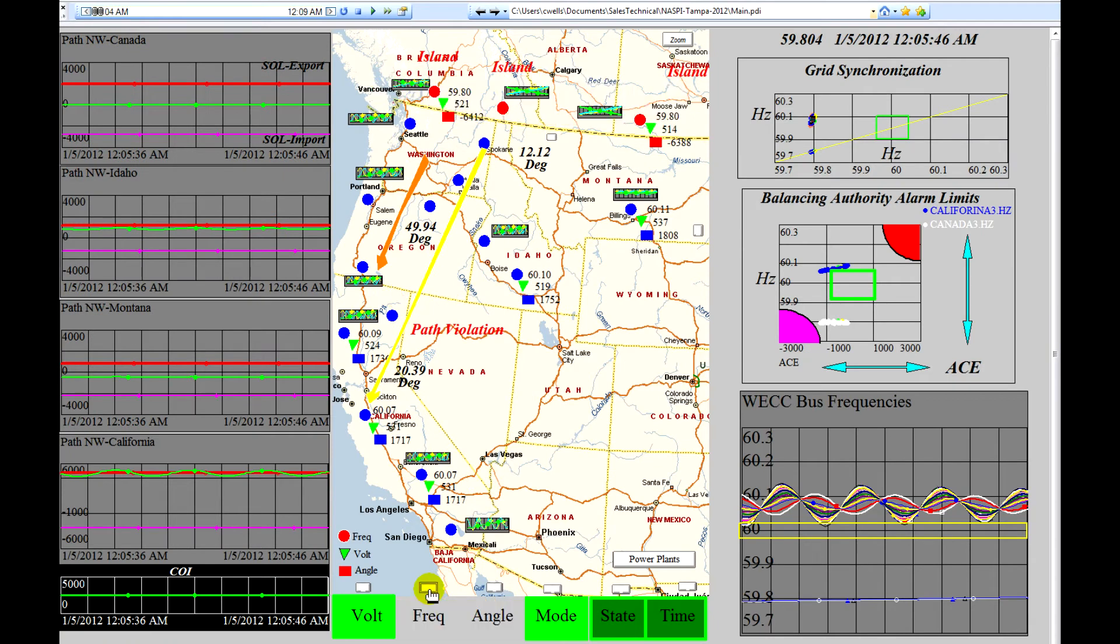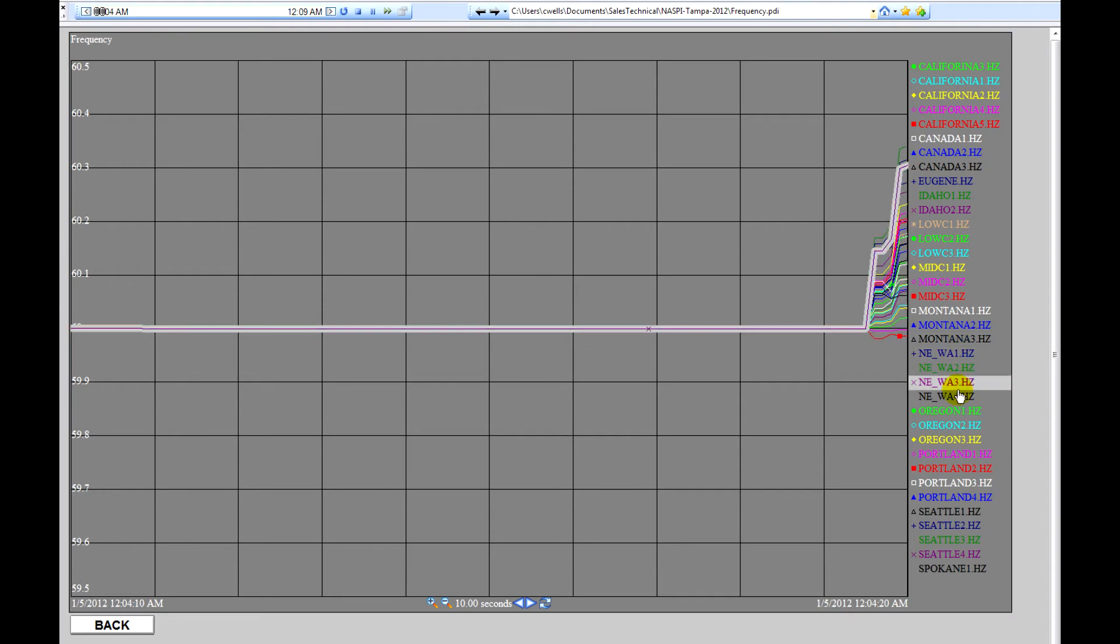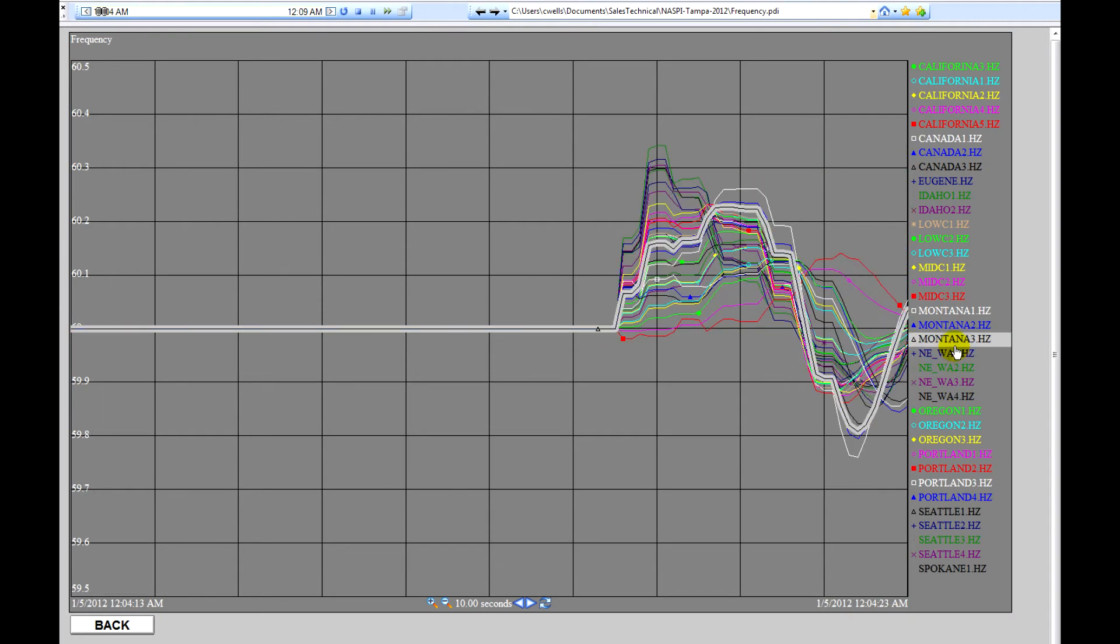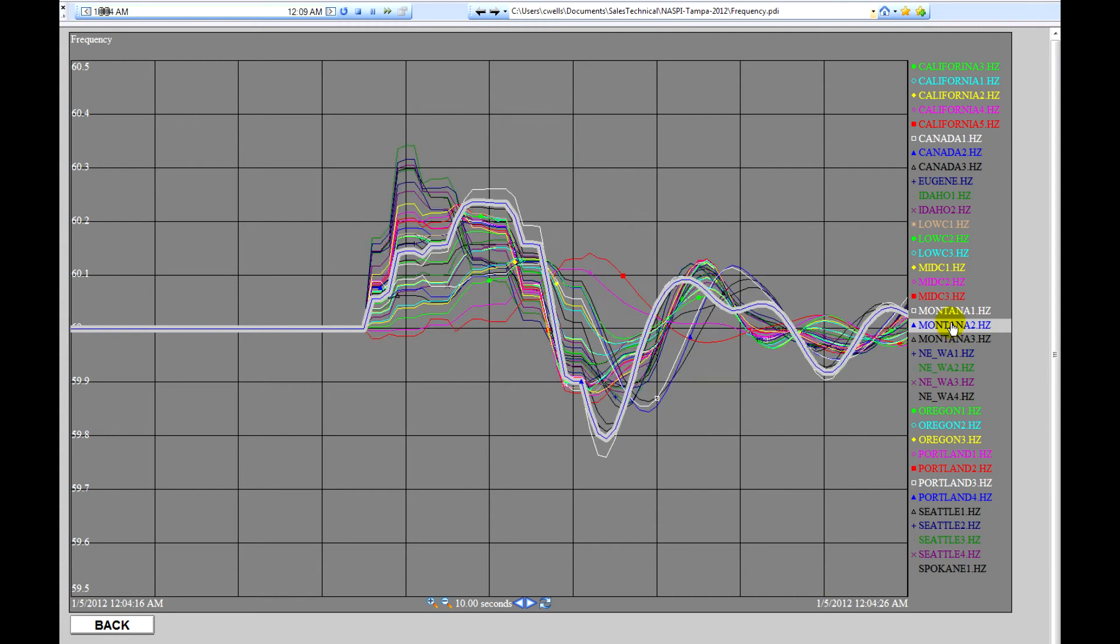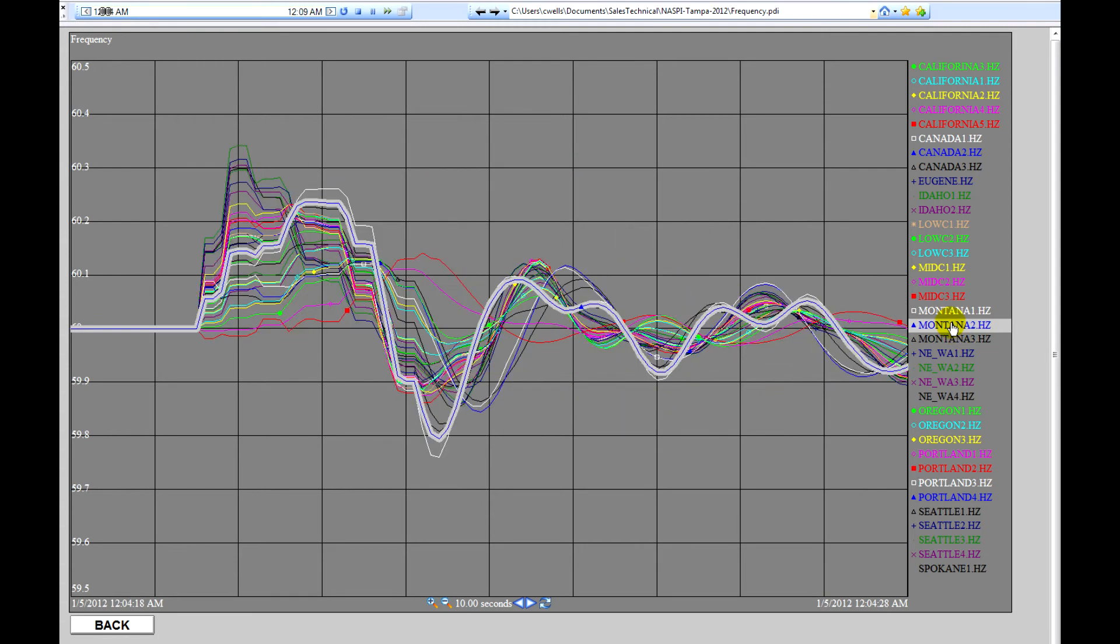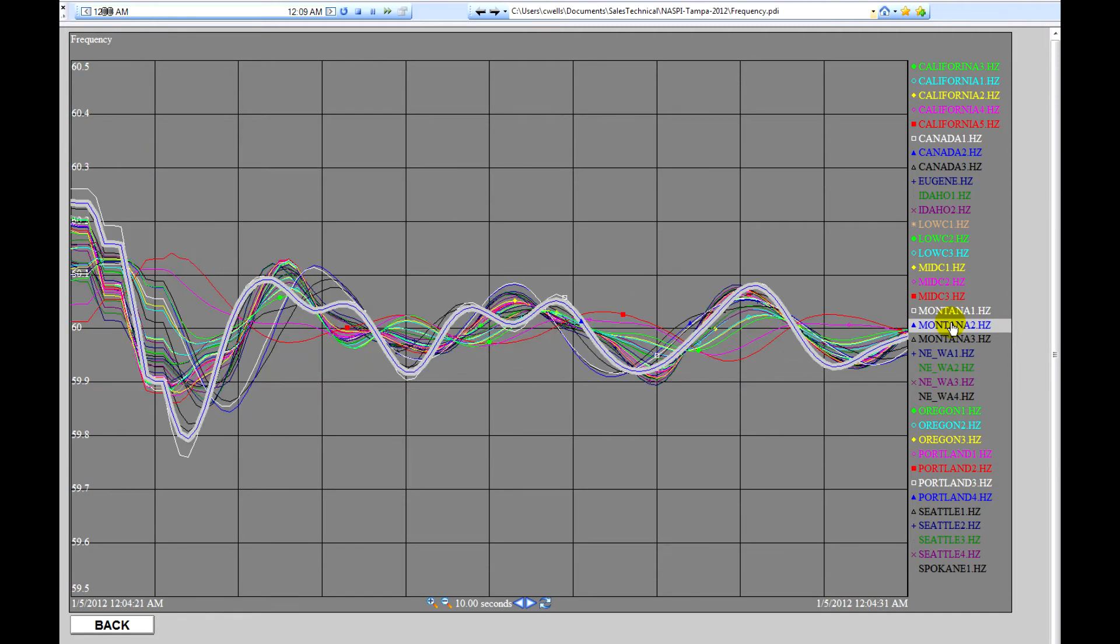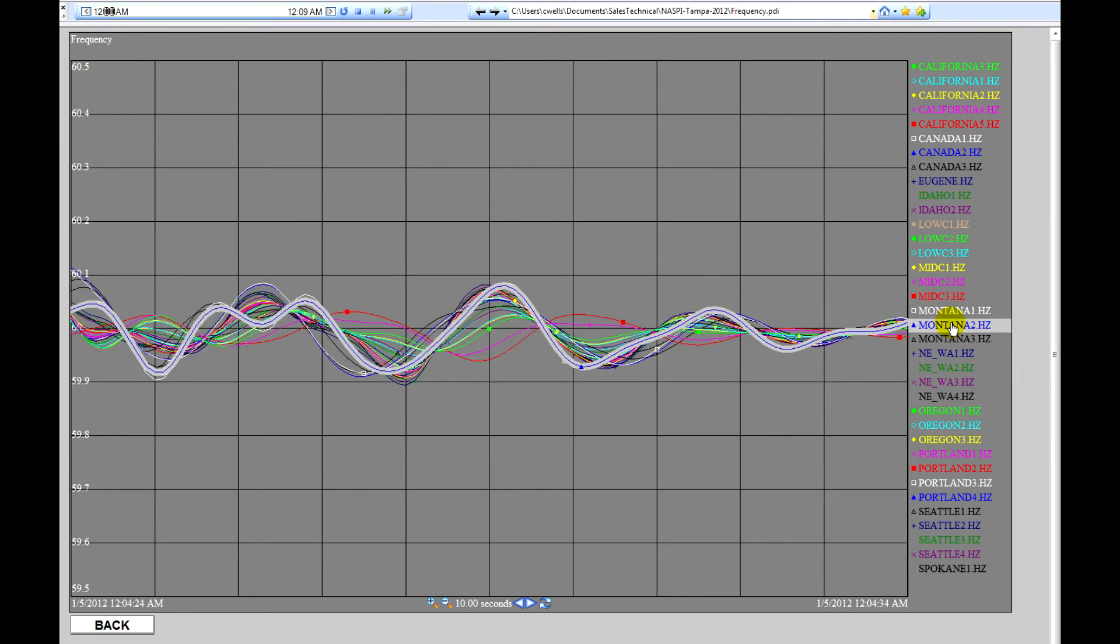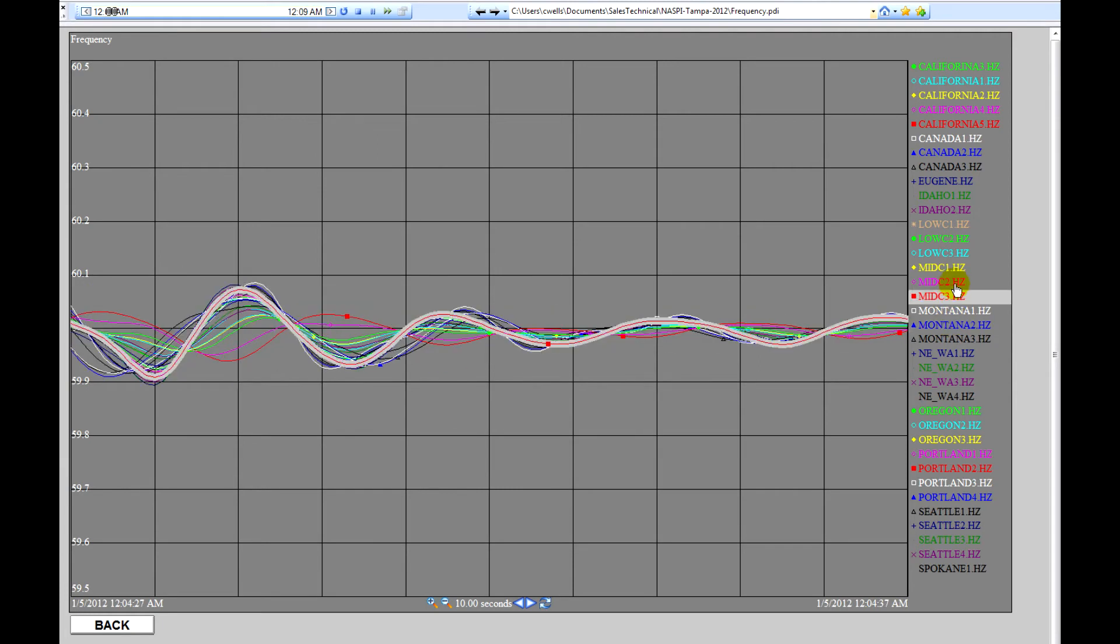We'll take a look at the frequencies. And the frequencies will investigate where the frequencies occur. Now, this is showing that all the frequencies in the WECC area suffered this initial disturbance. However, they all are coming back down to a normal range of oscillation.